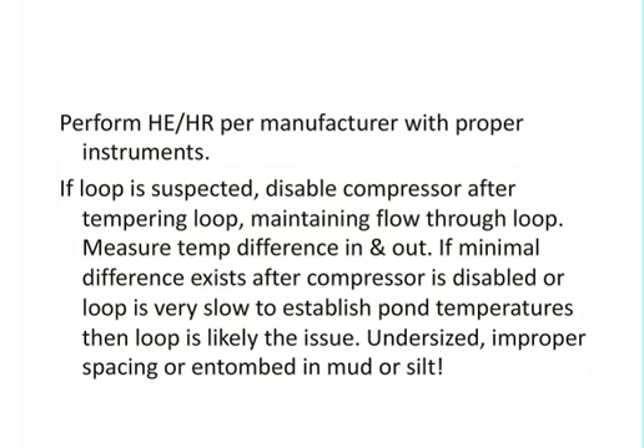If you suspect that the temperature difference going through the pond-style heat exchanger is where the shortcoming is, here's what you want to do. Again, run that heat pump for a bit in whatever the mode happens to be for that time of the year, and then just pull your Y1, Y2 connectors off and allow the pump to continue to operate. And you want to start measuring your temperature difference in and out. If there doesn't seem to be much difference in and out of that pond heat exchanger, again, when the compressor is turned off and you've already tempered that fluid, then you're not exchanging your temperature out there in the heat exchanger. Well, if you're not exchanging temperature, what are the causes?